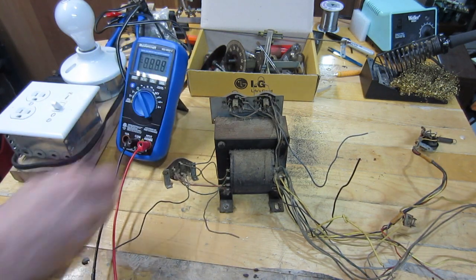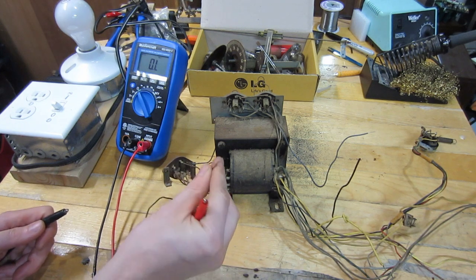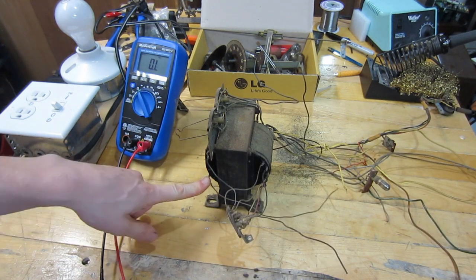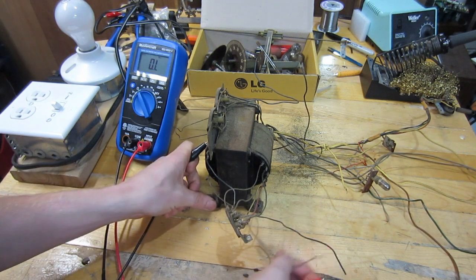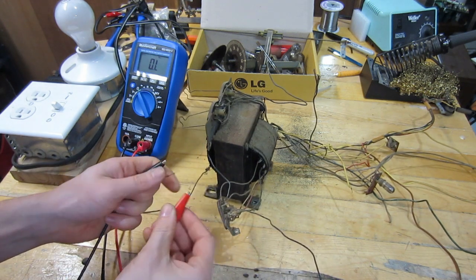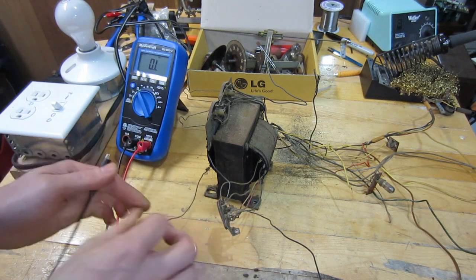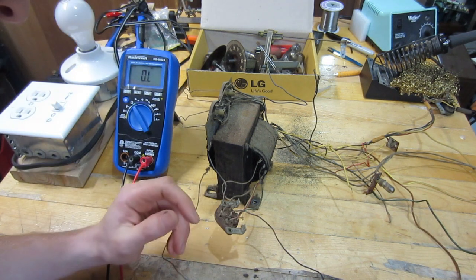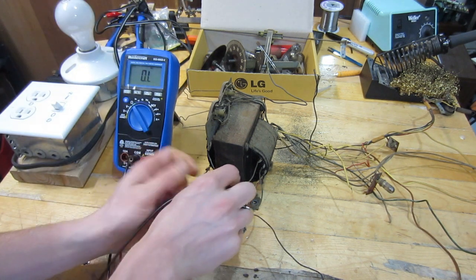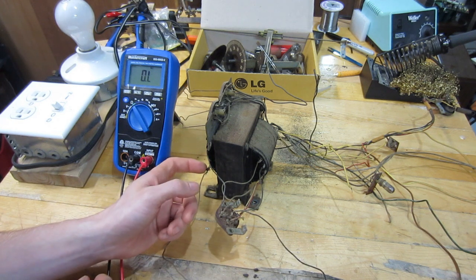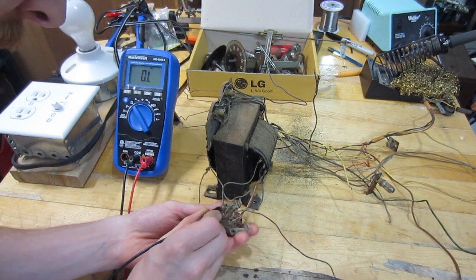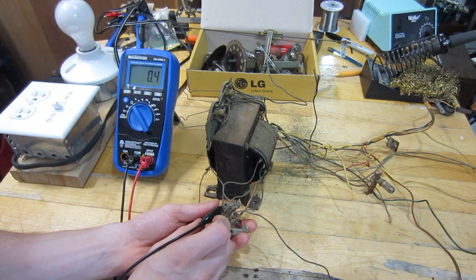So first thing I'm going to do is find my common wire, which turns out to be this tap right down here in this case. We're going to put one lead on here and measure resistance. I'm going to measure this wire here since it's closest to the common tap, and see what we get for resistance.